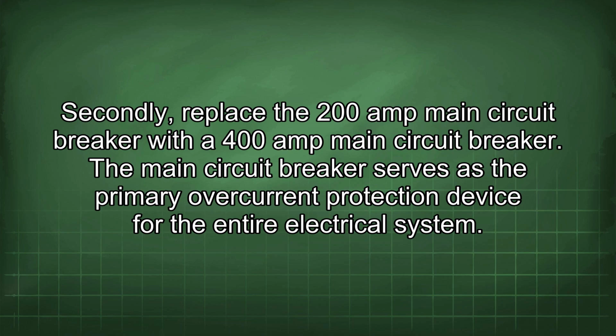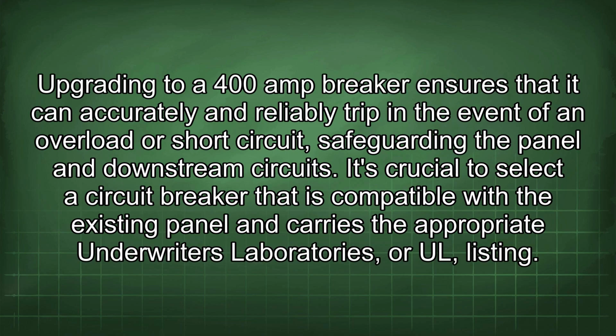The main circuit breaker serves as the primary overcurrent protection device for the entire electrical system. Upgrading to a 400 amp breaker ensures that it can accurately and reliably trip in the event of an overload or short circuit, safeguarding the panel and downstream circuits. It's crucial to select a circuit breaker that is compatible with the existing panel and carries the appropriate Underwriters Laboratories or UL listing.